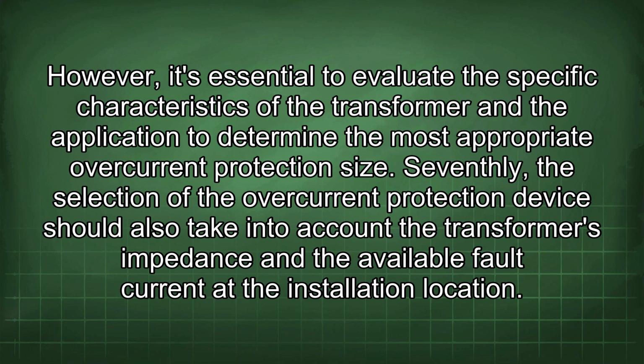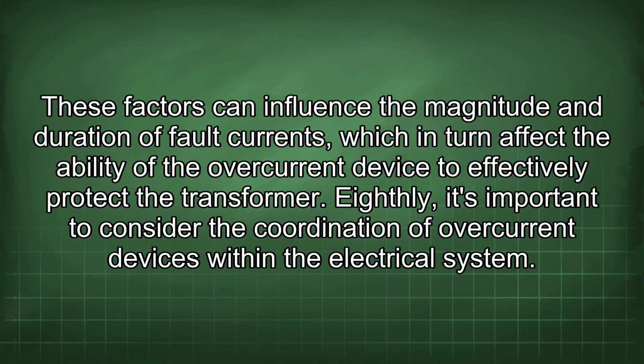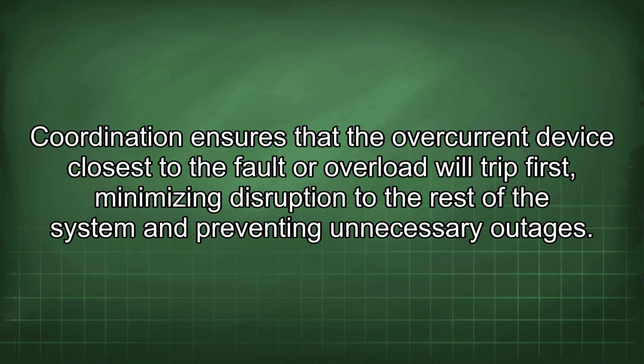protection size. Seventhly, the selection of the overcurrent protection device should also take into account the transformer's impedance and the available fault current at the installation location. These factors can influence the magnitude and duration of fault currents, which in turn affect the ability of the overcurrent device to effectively protect the transformer. Eighthly, it's important to consider the coordination of overcurrent devices within the electrical system. Coordination ensures that the overcurrent device closest to the fault or overload will trip first, minimizing disruption to the rest of the system and preventing unnecessary outages.